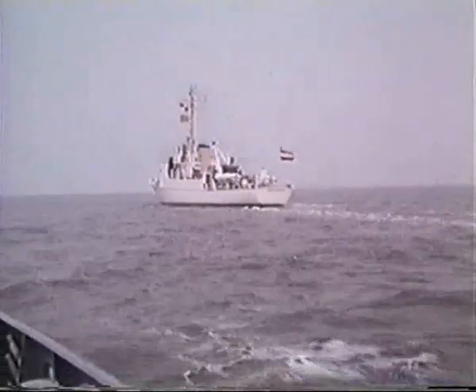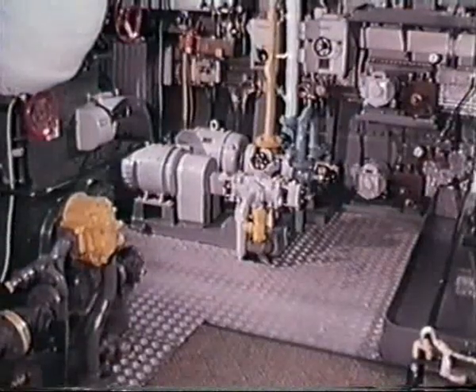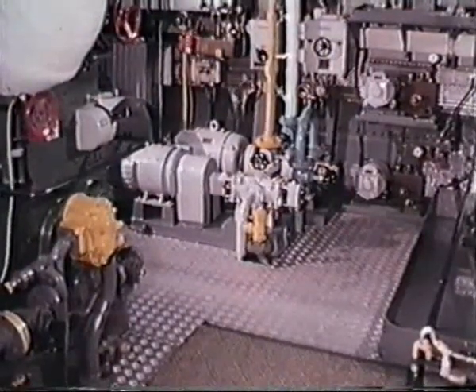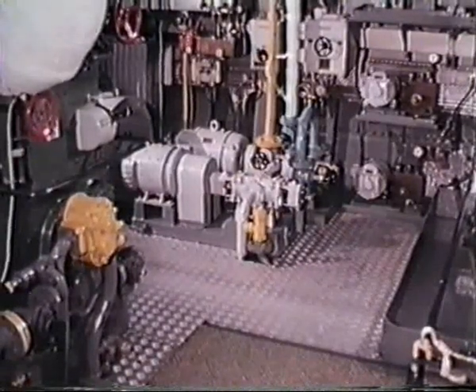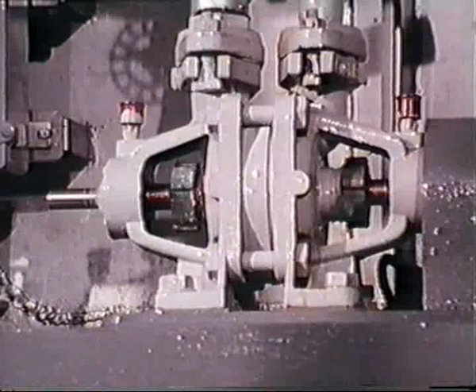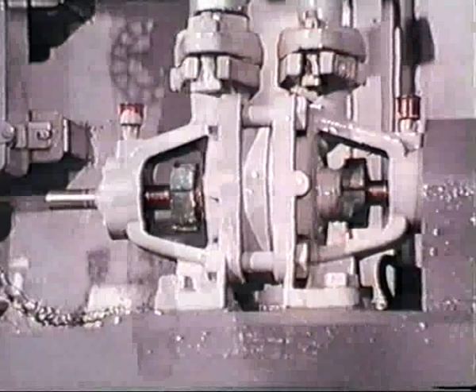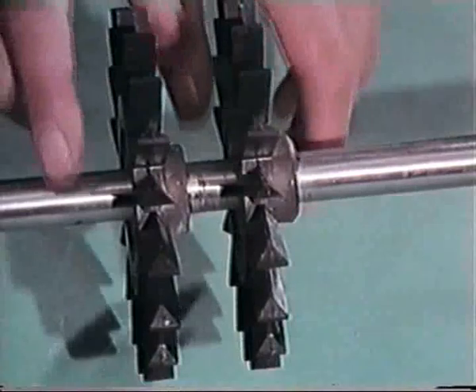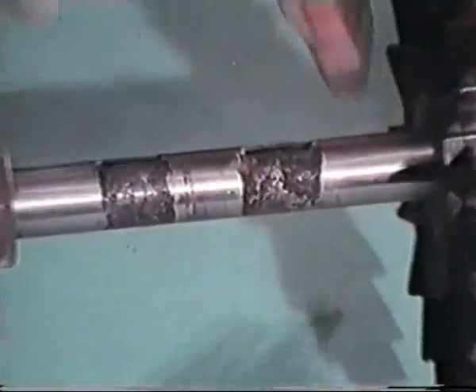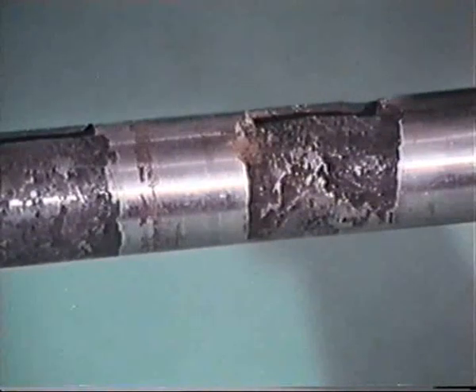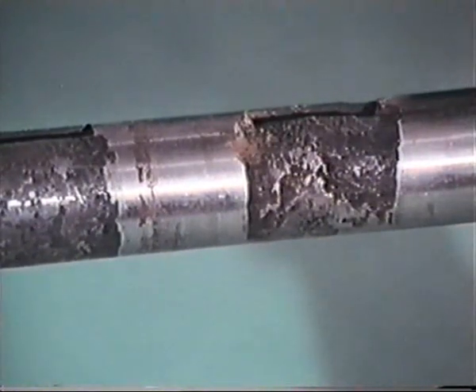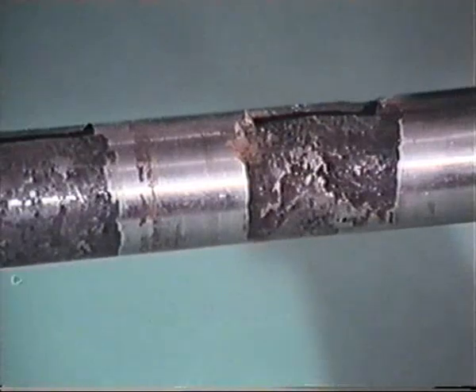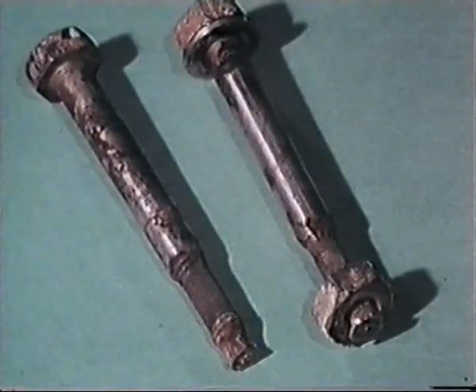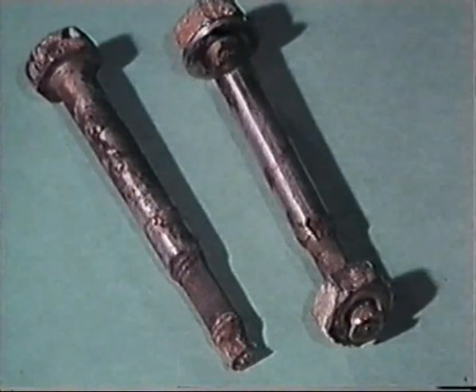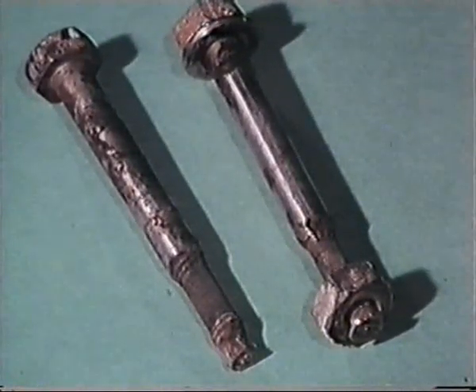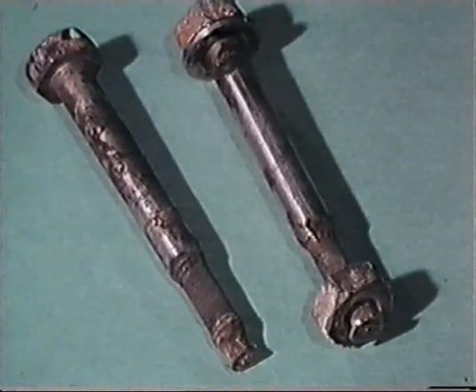Seawater is very aggressive to metals. It will even attack stainless steels, especially if a crevice is formed. This is a problem in pumps, where in idle periods the stagnant conditions may allow crevices to corrode. It can be overcome either by flushing with fresh water before shutdown, or by using different materials. Threads, too, form crevices, and stainless steel bolts can suffer attack in seawater. The remedy is the use of especially resistant metals.